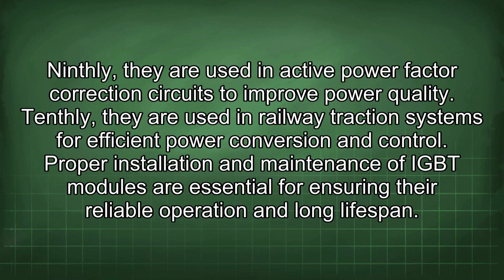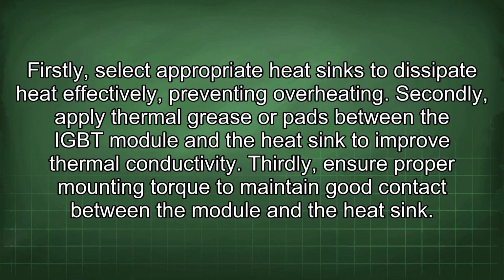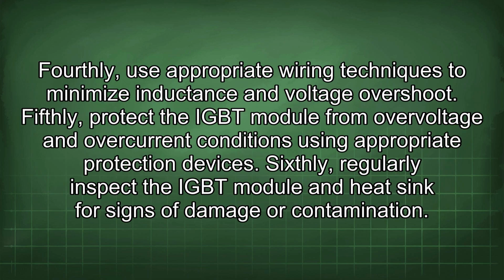Proper installation and maintenance of IGBT modules are essential for ensuring their reliable operation and long lifespan. Firstly, select appropriate heat sinks to dissipate heat effectively, preventing overheating. Secondly, apply thermal grease or pads between the IGBT module and the heat sink to improve thermal conductivity. Thirdly, ensure proper mounting torque to maintain good contact between the module and the heatsink. Fourthly, use appropriate wiring techniques to minimize inductance and voltage overshoot. Fifthly, protect the IGBT module from overvoltage and overcurrent conditions using appropriate protection devices.